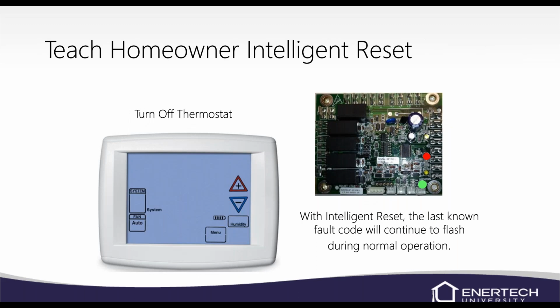Basically, the homeowner can go to the thermostat, turn it to the off position, and wait 30 seconds to a minute. They can put it back into heating or cooling, whatever they were in, and it will hold the code on the lockout board of the last fault. It'll also allow it to try to recycle itself 3 more times. And then if it's still locking out, it'll say call for service again on the thermostat. Now, I wouldn't have the homeowner keep resetting it at the thermostat. Maybe one time, and if it still locks out, then they need to call somebody out to look at it.